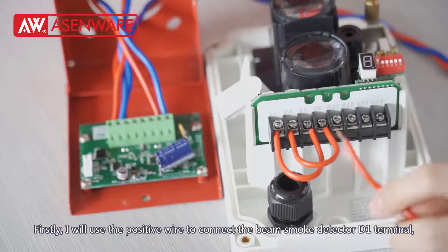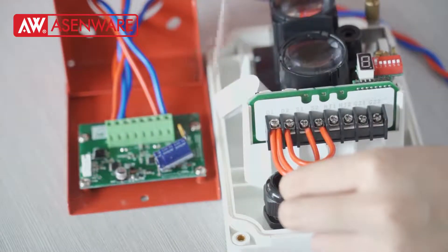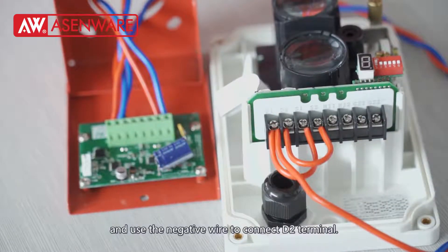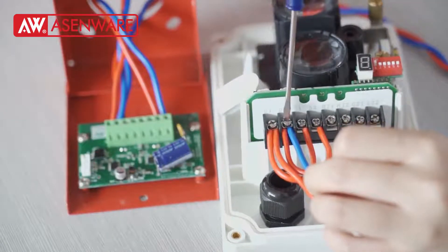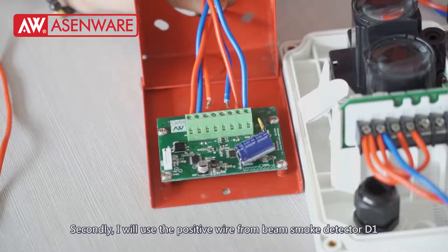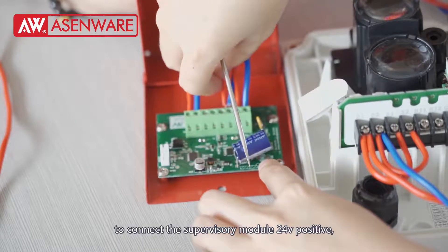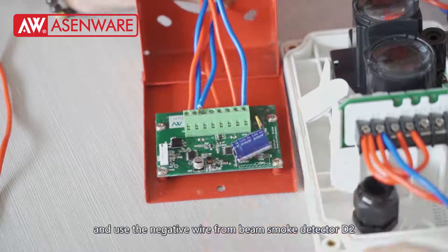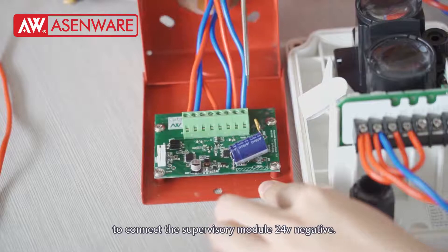Firstly, I will use a positive wire to connect the beam smoke detector D1 terminal. And use the negative wire to connect the D2 terminal. Secondly, I will use a positive wire from beam smoke detector D1 to connect the supervisory module 24V positive, and use the negative wire from beam smoke detector D2 to connect the supervisory module 24V negative.